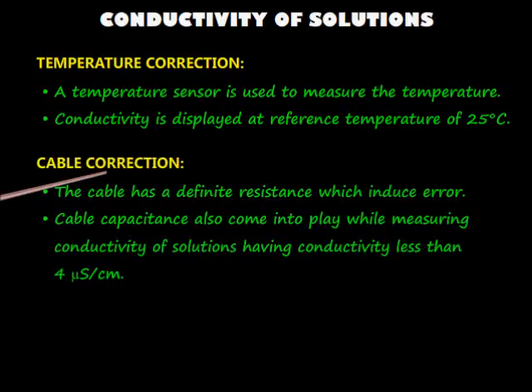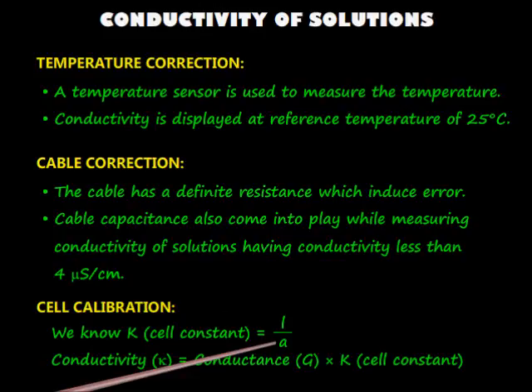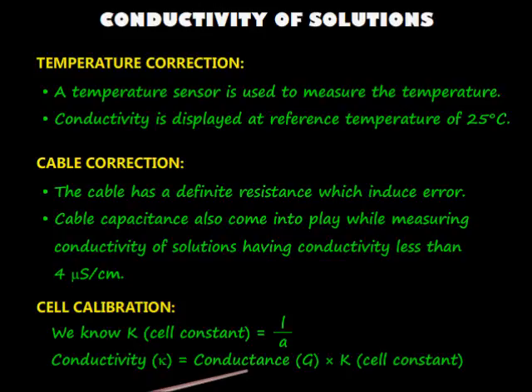Temperature of the solution is another aspect which can lead to false conductivity measurements. To perform correct conductivity measurements, a temperature sensor must be used such that the conductivity may be displayed at a reference temperature of 25 degrees Celsius. Cable correction should also be done while measuring conductivity of solutions having very low conductivity. Normally, we do not measure L and A for a cell to determine its cell constant; we rather measure the conductance of a solution with known conductivity and calculate the cell constant from there.